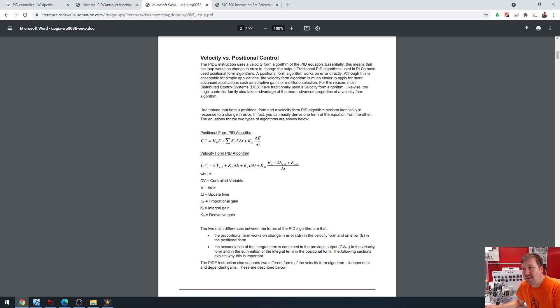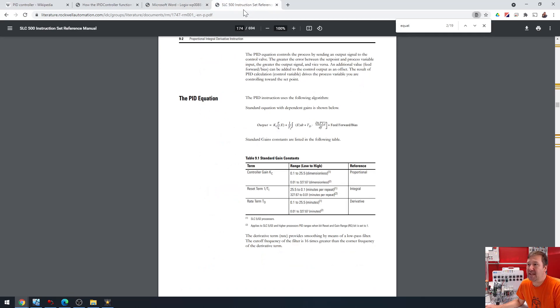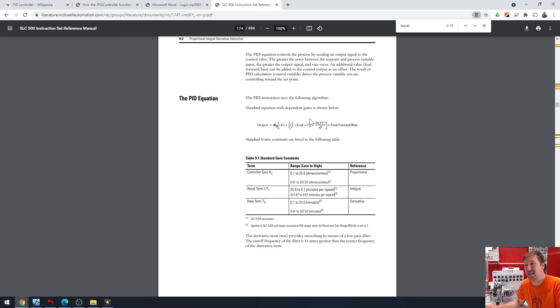And so the gain is multiplied by the error, strictly. Kp is our proportional gain, and E is our error. But in the case of the SLC 500, it's a dependent equation. In this case, Kc is our gain, and it's multiplied by the error, the integral calculation, and the derivative calculation. So that's a dependent equation.